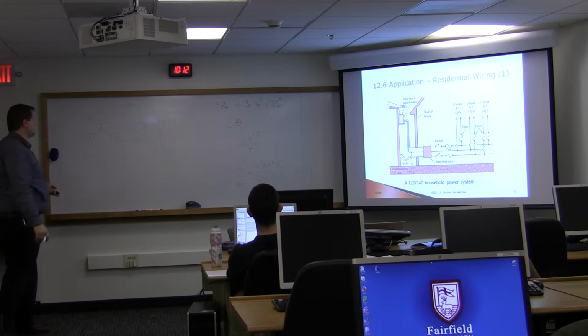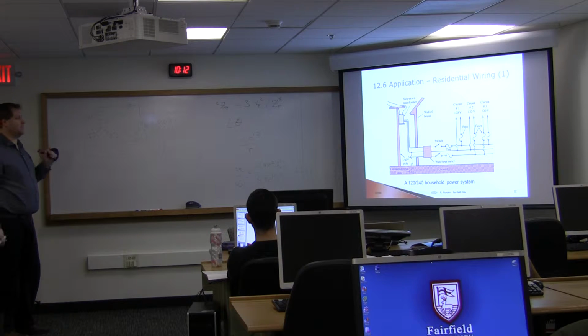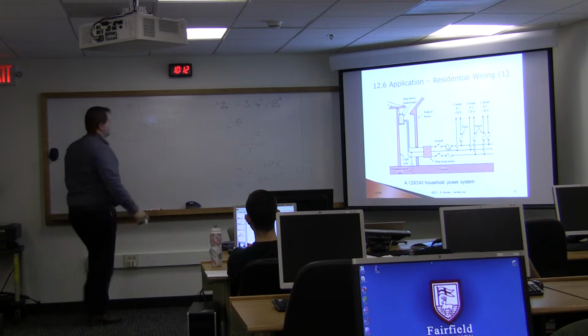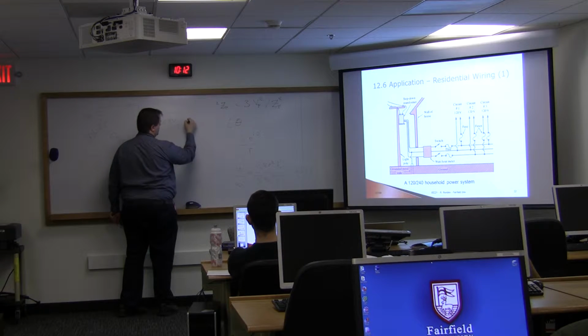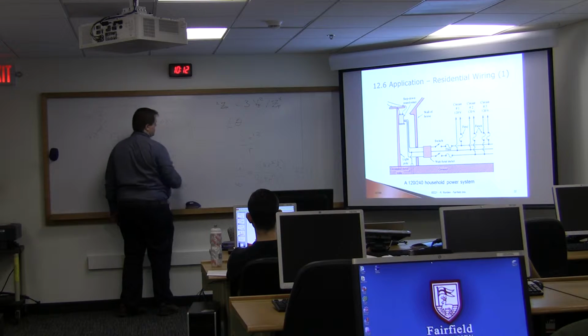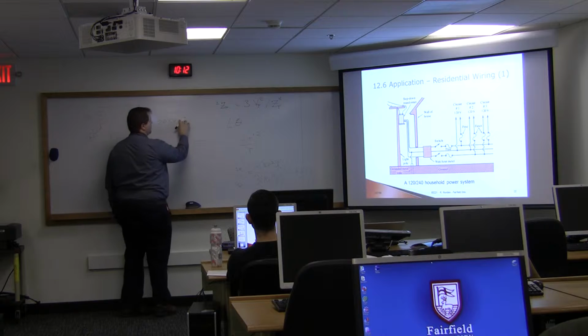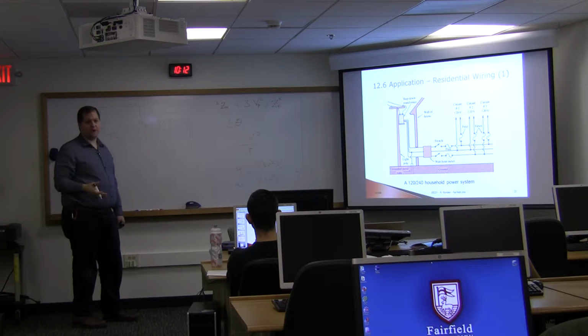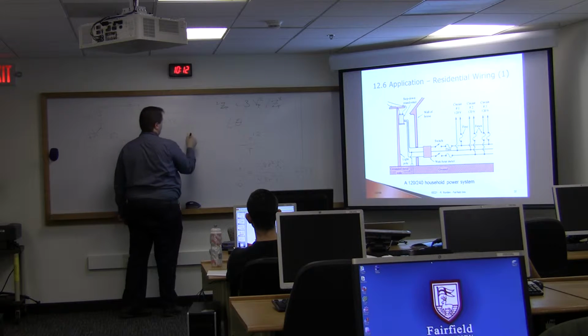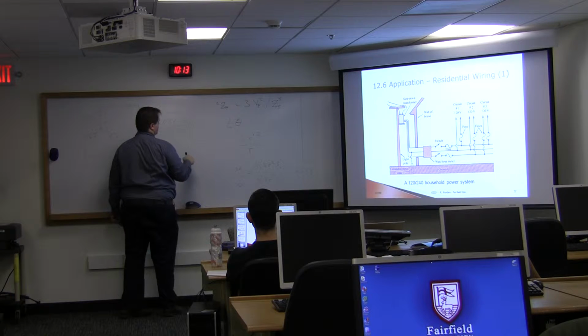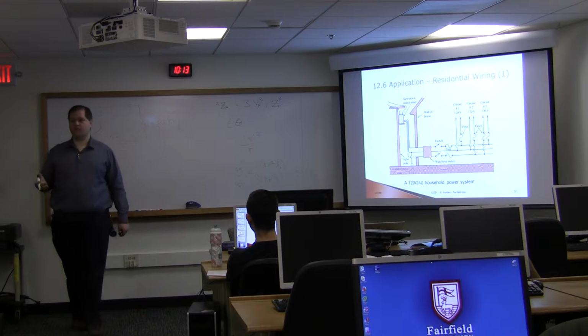So when you look at a distribution panel, which you did a lab with last semester, if you're looking at a circuit breaker panel, there's a bar down the middle, and they run the two phases off each of the sides. You can connect to one to get a single 120 volts, or you can connect a double breaker—sorry, it actually jumps across like this. There are more on the other side of the distribution panel, but every other slot connects to one of the two different lines coming in. So if I connect across both of those, I'll get a 240 volt system.